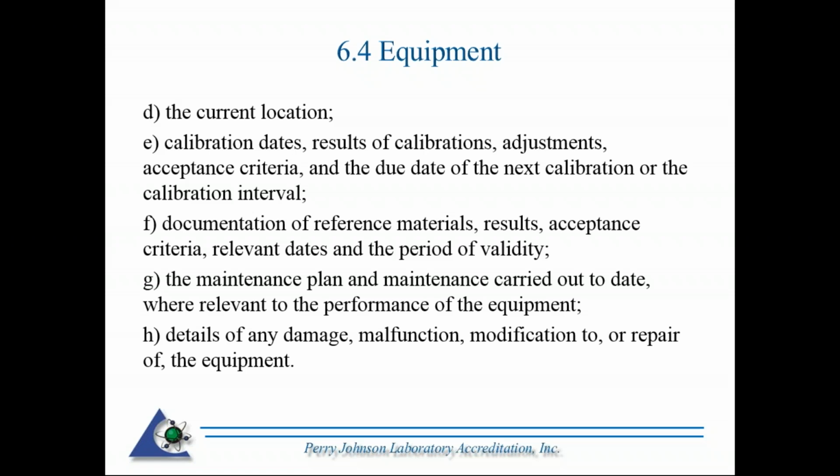Then the maintenance plan and maintenance carried out to date, where relevant to the performance of the equipment. Also details of any damage, malfunctions, modifications to, or repairs of the equipment. A record needs to be maintained within the lab, detailing exactly what was done and what happened.